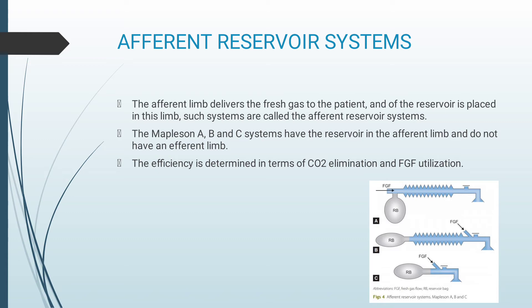Mapleson C is identical to Mapleson B except that the corrugated tubing is omitted. The afferent reservoir systems can be used during spontaneous respiration, and require at least two to three times the minute ventilation as fresh gas flow to avoid re-breathing. The main problem with these systems during controlled or assisted ventilation is that as pressure remains low during exhalation, no gas escapes through the APL valve, and all the gases — both dead space and alveolar gas — remain in the corrugated tubing and are delivered to the patient during the next inspiratory phase.